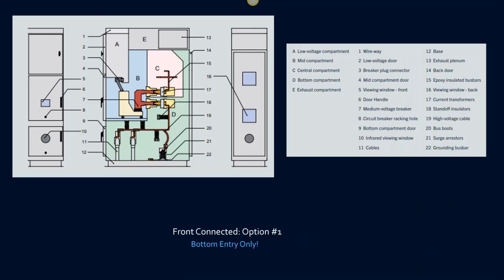So here's one solution, and there's a few manufacturers that make this type of gear, and this is really IEC gear that's been ANSIfied. And ANSIfied is my cute word for bringing IEC gear into the US and making the necessary modifications, if any, to test it to the NEMA standards. So you can see here the bottom is the cable connection compartment, and the middle portion here is the breaker compartment. And so obviously one limitation here is this is a one high design. There is no two high design for this particular manufacturer.